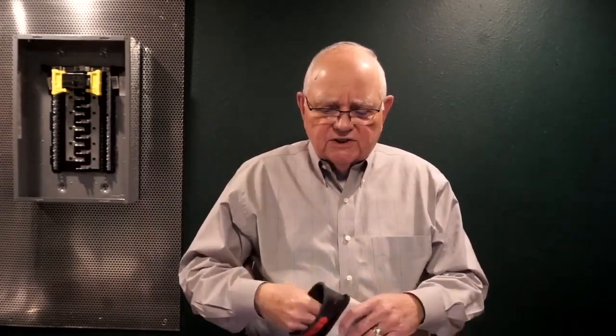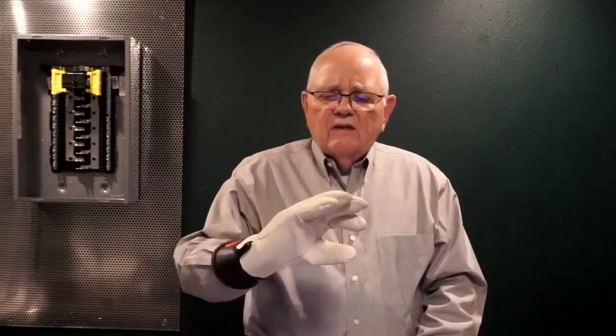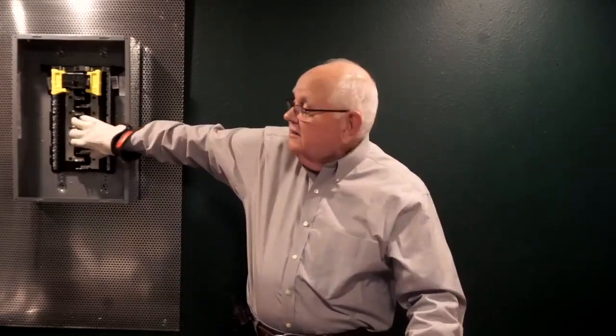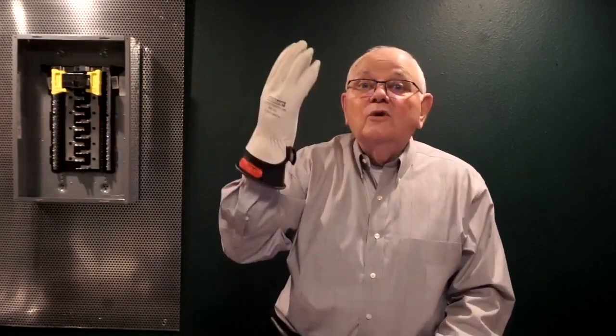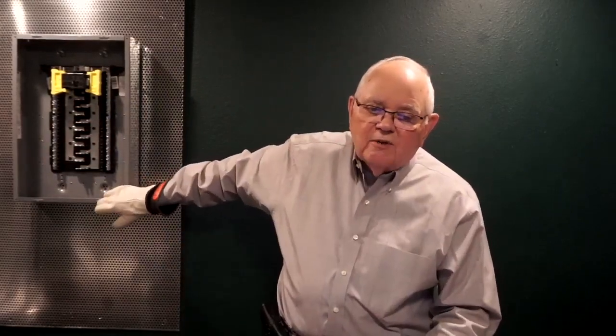Now, one of the requirements of NFPA 70E, it talks about PPE. So for instance, for shock protection, what do we have for personal protective equipment? And that's our insulated rubber goods. So our insulated rubber gloves, for example. And that's my last line of defense. I would never put this on my hand and say, I can go back here and touch this energized circuit and it can't hurt me because I got on my rubber glove. That would be crazy. That would be insane. So we would never do that. The only reason that I wear my rubber glove is in case I'm in here doing something and I accidentally touch something I shouldn't, I don't get myself shocked. So that's a good thing.